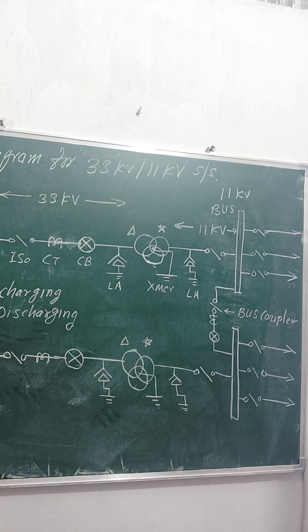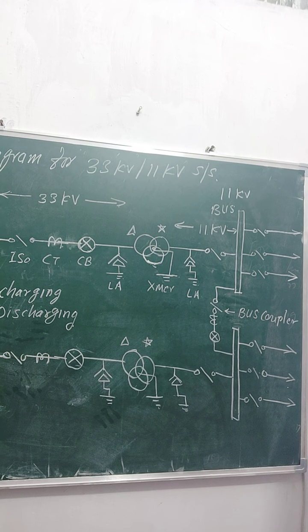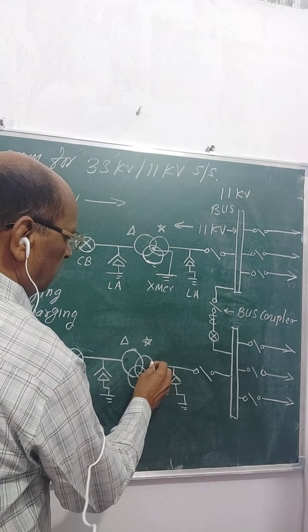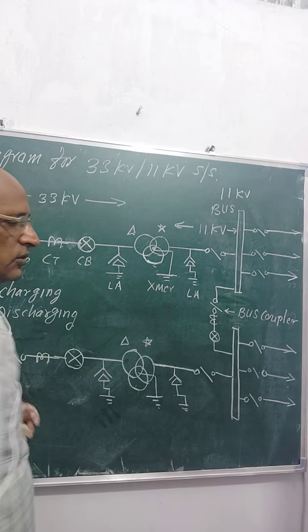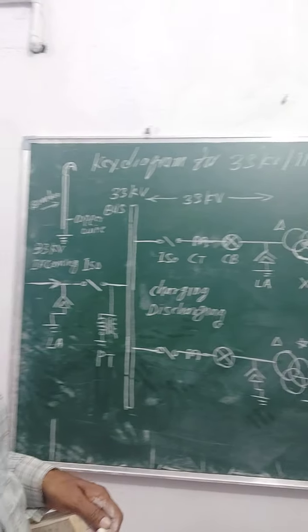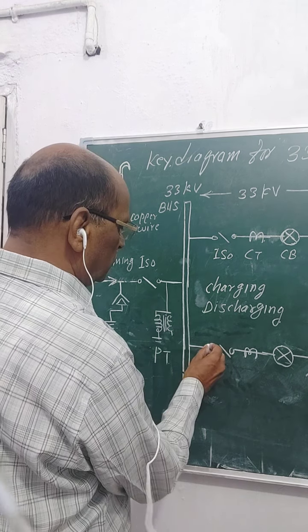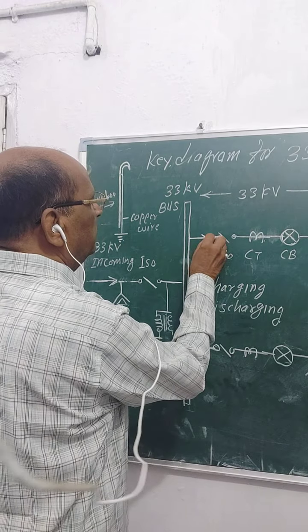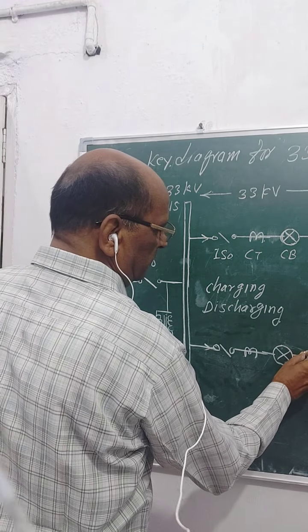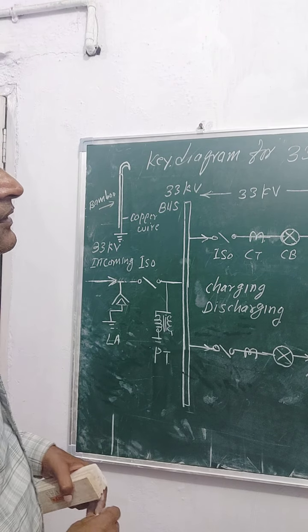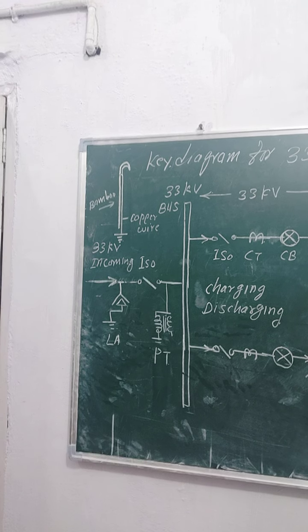So this particular portion we put on the conductor. Whatever voltage is there, even after we switch off the complete substation, due to residual magnetism, there is some voltage present on the conductor. So before going for any maintenance activity, we should discharge the complete equipment, the bus bar and conductors. Then only we start its maintenance.